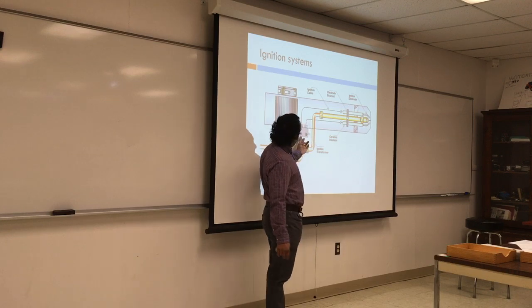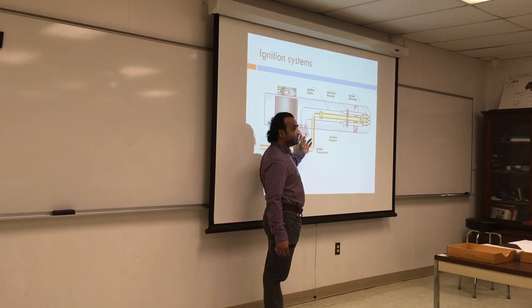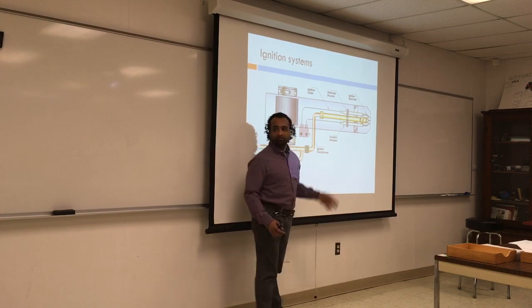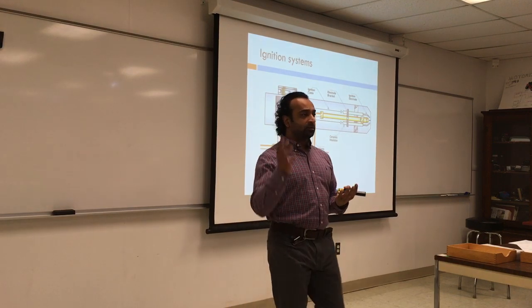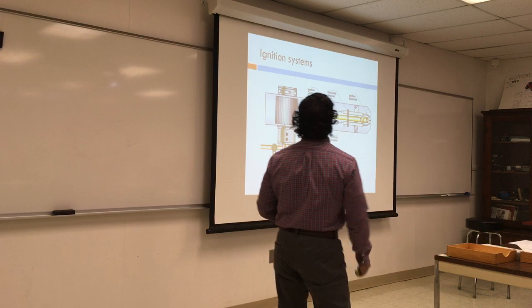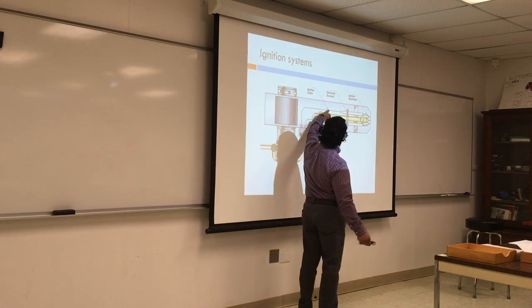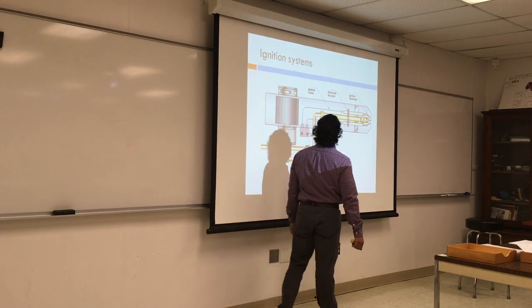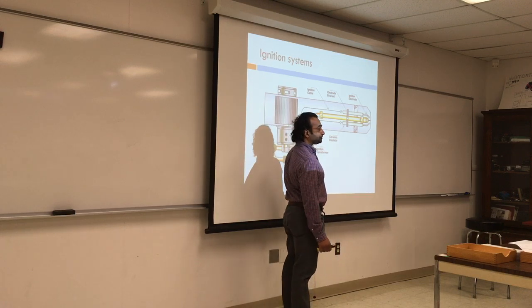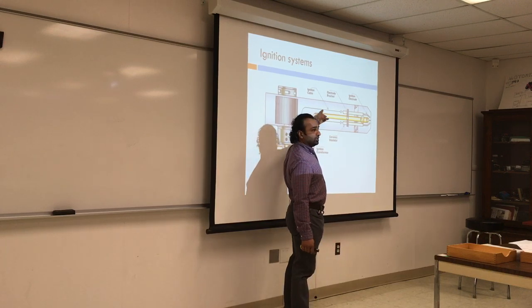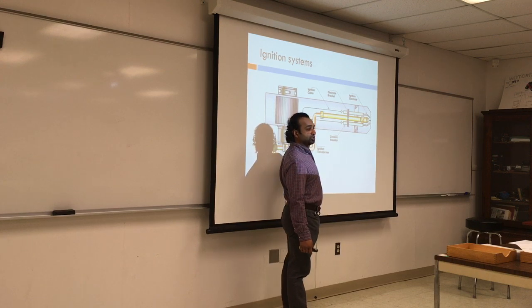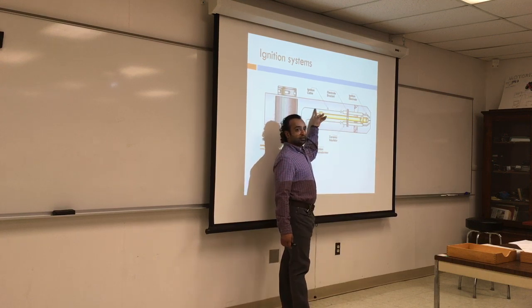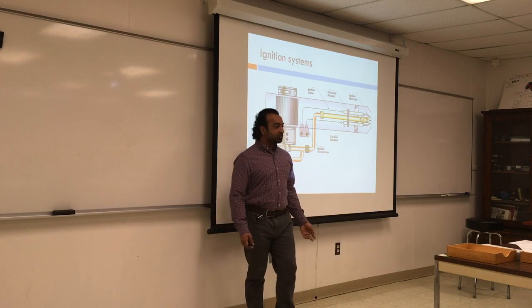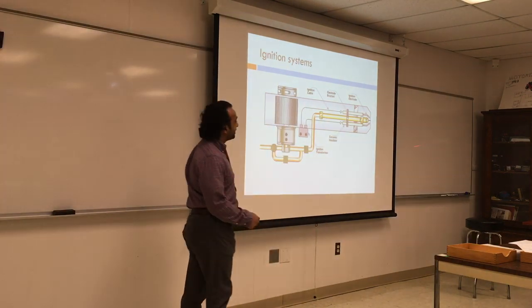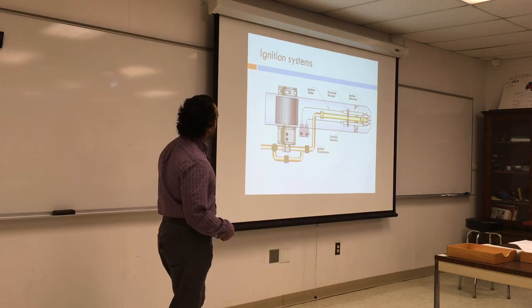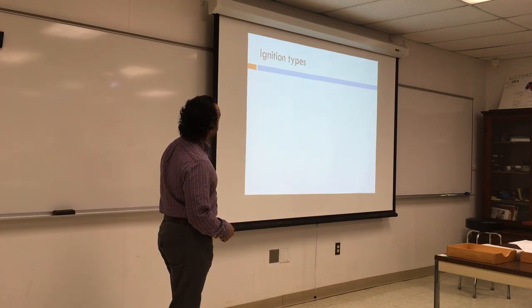Again, sometimes we have an ignition transformer from the outside connected through wires, or sometimes we have the big transformer that actually hits the bus bars. Those are called the bus bars or ignition cables. In many cases, especially with the Beckett models, the connections are not really well made. So as you close everything, those will disconnect and you don't have ignition. So it's good to verify that you have ignition and a spark at the end before you start burning.